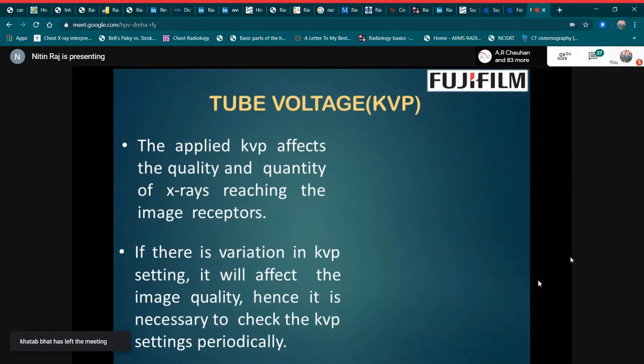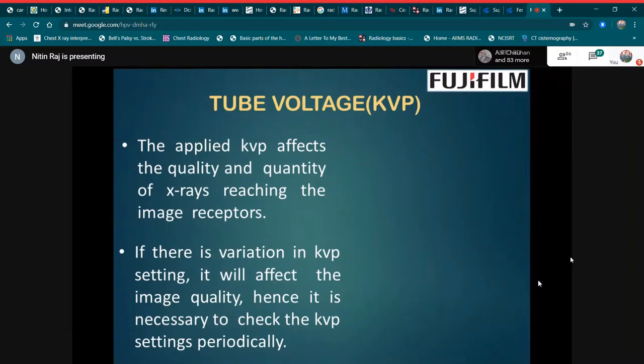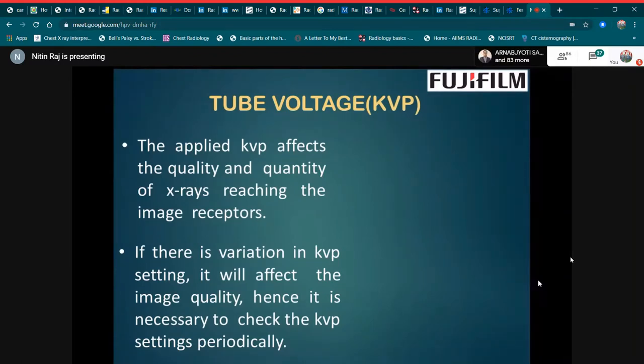Next is tube voltage. The applied kVp determines the quality and quantity of the x-rays reaching the image receptor. If there is variation in the kVp setting, it will affect image quality. Hence, it is necessary to check the kVp setting periodically.